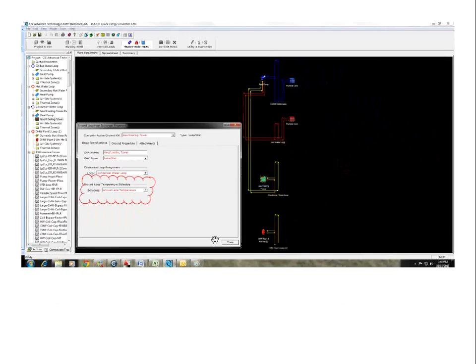I had to play around with these dates because I believe what was happening was that when the building ran, it needs cooling on those shoulder seasons in the fall and the spring. I'd run it with different dates in there. Basically, it was arbitrary or best guess to get it to work. This is telling it that from January 1st to March 31st, the geothermal is on, and the loop temperature being provided is 90 degrees. Then from that until November 15th, the cooling tower is on, and the temperature of the loop is 80 degrees. And beyond that, it goes back to heating, which is 90 degrees. Like I said, I had to mess around with those dates to get it to work.